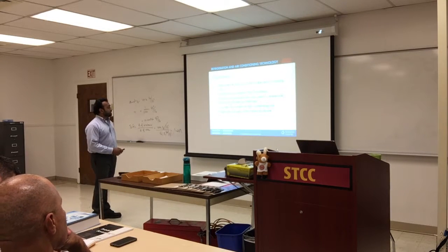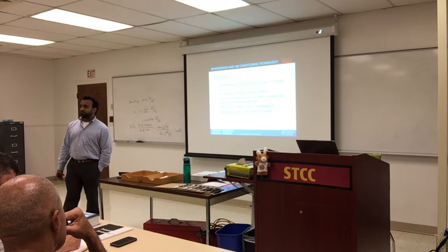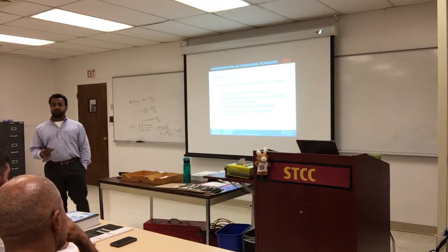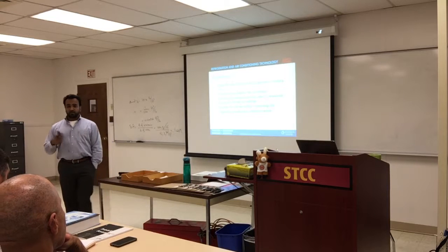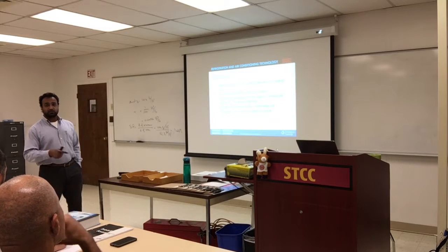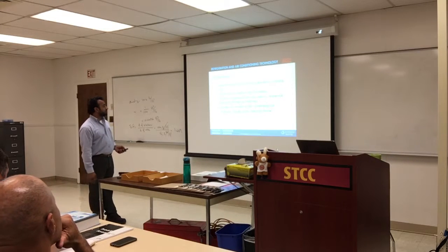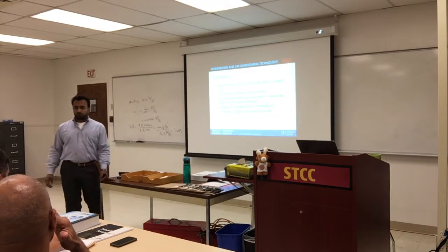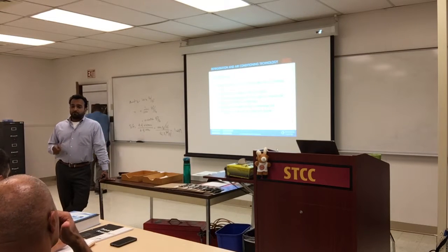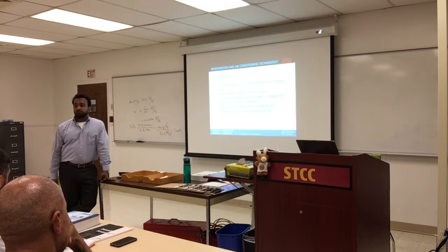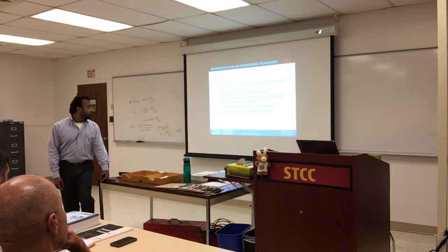We'll talk about the compressor that's normally used in residential and light commercial buildings. There are majorly two types of compressors. Either the piston one that functions like a car motor or engine, or the scroll one that keeps turning and squeezing the volume of air until it's compressed. It looks like a corkscrew pump, but it goes in a spiral and just compresses the air. They are quieter, they have a lot of advantages, they're more expensive, and sometimes they are hard to repair.